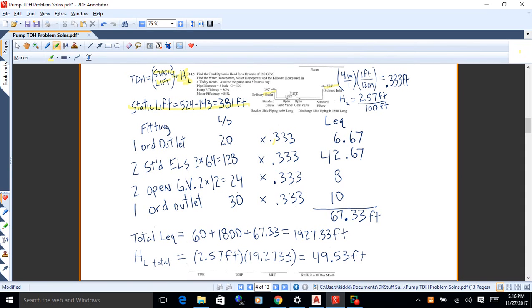The head loss is a little bit trickier. There's a few steps with that. So we've got 4-inch pipe, so we can convert that into feet. It's 0.333 feet. And the head loss for this particular situation, which is 150 gallons per minute going through 4-inch pipe C100, the head loss for that is 2.57 feet per 100.